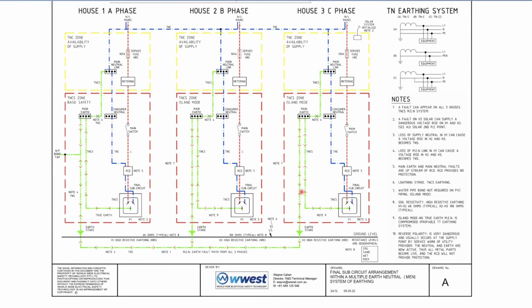If you get rid of your water pipe, your gas pipe, and just have your earth stake, then you've got no earthing points inside this house here, like in your wet areas. And combine that, as I said before, with your building codes and your wet areas, all the fiberglassing that they do with wet sealing and everything like that. So you've lost, in modern day housing, your basic safety of the TNCS earthing system. Thank you for your time.